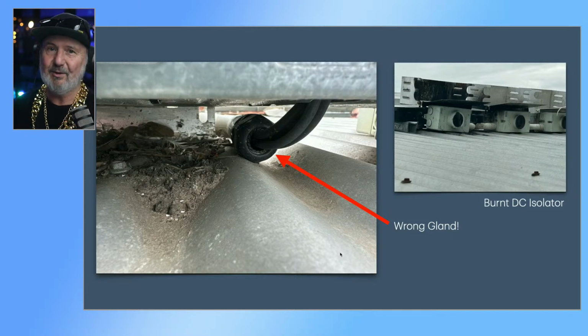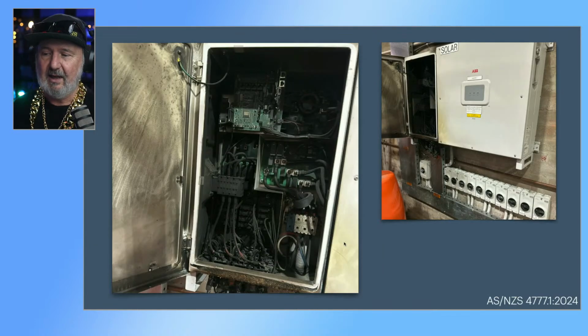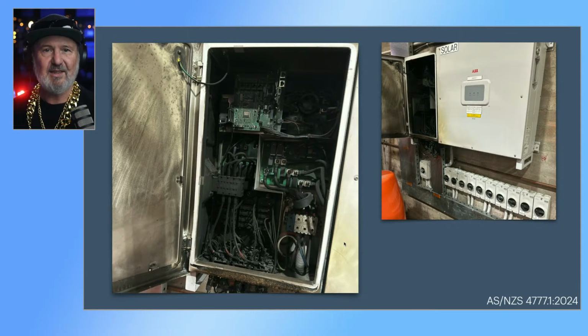So cables are great at becoming drip lines. Water runs down the cable, goes straight in that hole, through the plumbing system, known as conduit, into the isolator and catches fire. So, yeah, that was pretty disastrous. And that's the ABB large inverter. Gee, just check out how many DC inputs that has. And it just basically incinerated the whole thing. So it's still under investigation.